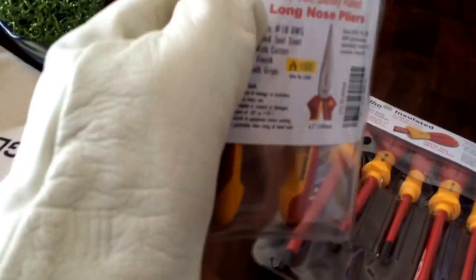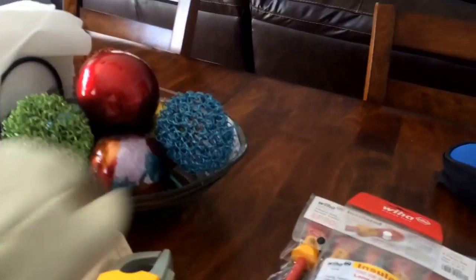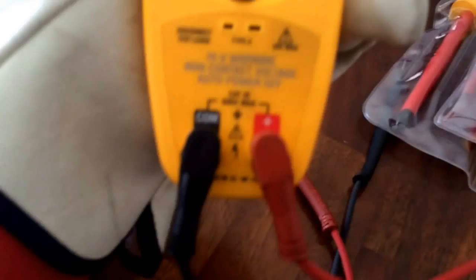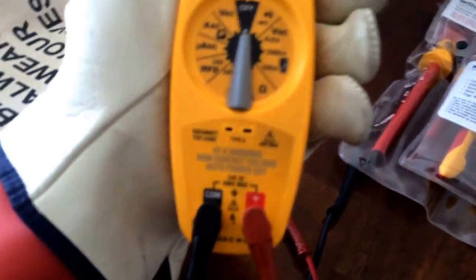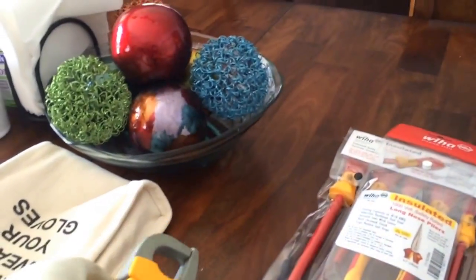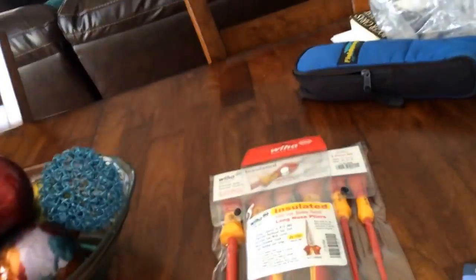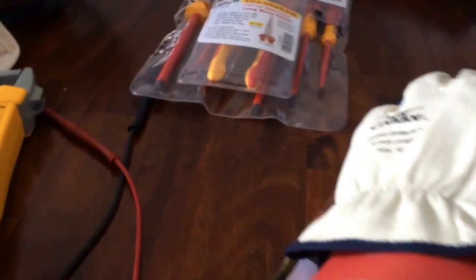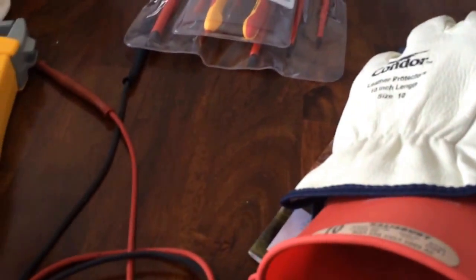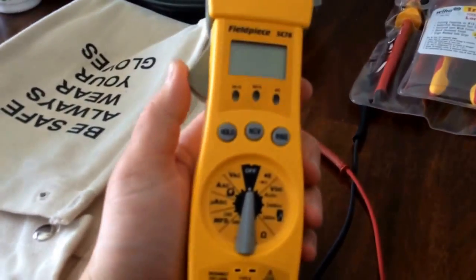I don't believe they make an insulated tool under 1,000 volts anyway, don't quote me on that. But when you're working with meters and things like that, make sure you check the rating and know what category it is. Like I said, this one is a category 3, 600 volts max. Most of us aren't working over 600 volts in the HVAC world—usually up to 460, 480—so a meter like this will suffice.